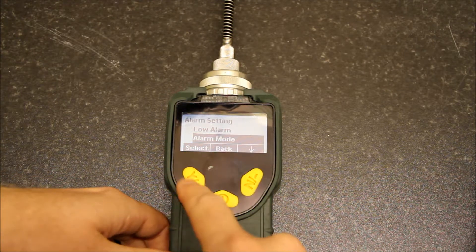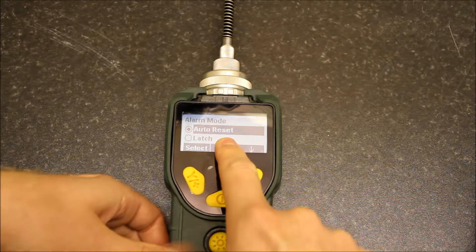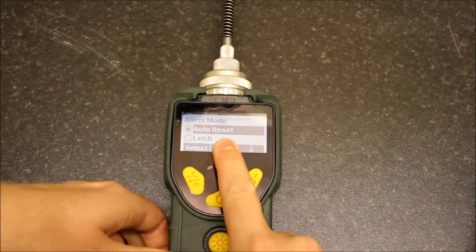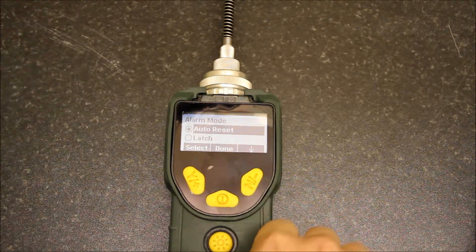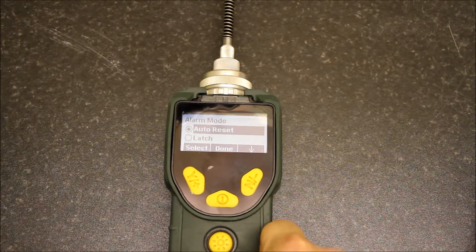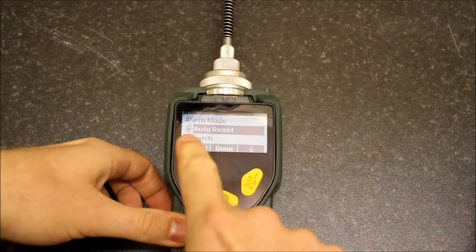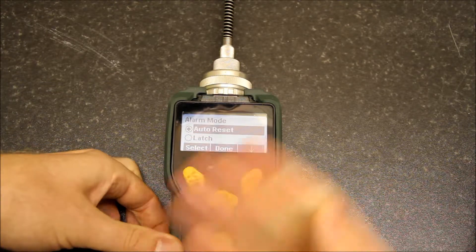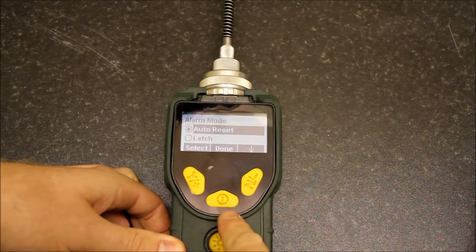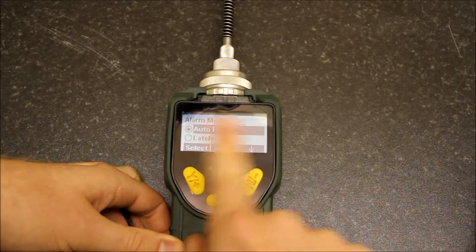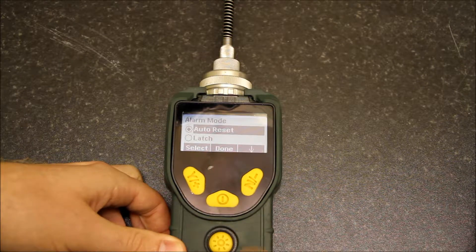You can go to alarm mode here. You've got auto reset, which is where the unit goes into alarm when it detects a sufficiently high level, then clears down automatically. You've got latching, which means when it drops into alarm you have to press a button to drop back out. Mine's in auto reset.